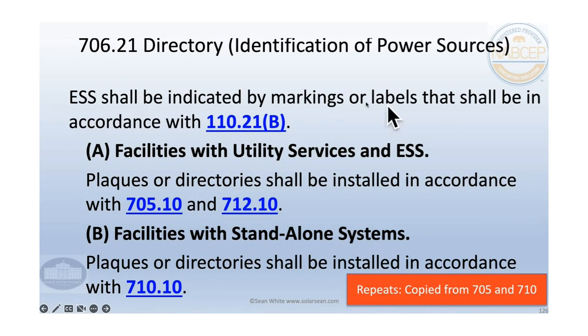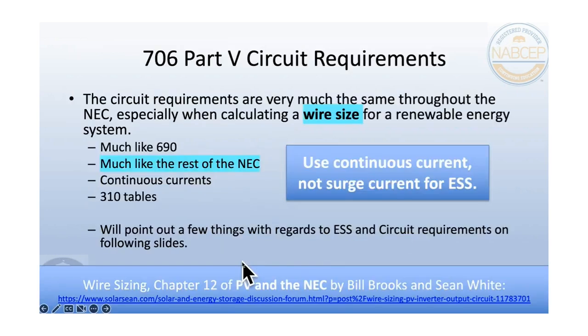Identification of power sources. So we have the labels in accordance with 110.21(B), which tells us how our labels are recommended to be weather resistant and not in handwriting and things like that. And so we need to have plaques. You're going to have a placard or a plaque or a directory that's going to show the firefighters that when they turn something off, they make sure they get everything, if you have different disconnects in different places. So if you have all of your disconnects in one place, like it's all right by the meter, that's the best way. And you just need one plaque or directory, something that tells you what to turn off. And if you have different things in different places, different sides of the buildings, then you need a plaque on different sides of the buildings. And then also when you have a standalone system, you're going to, of course, need to have some place outside where it's going to tell somebody where to turn it off, and that's going to be in 710.